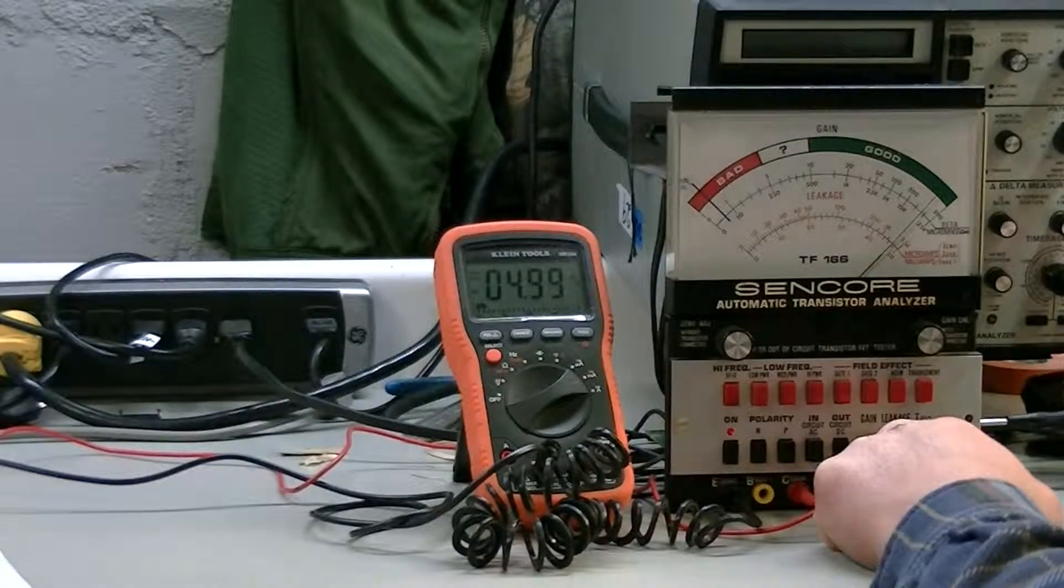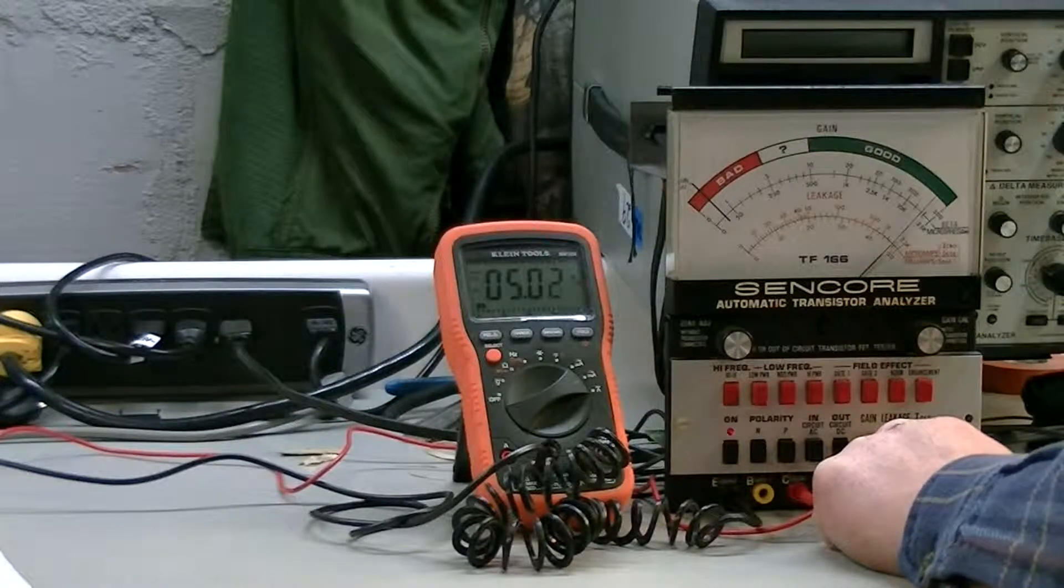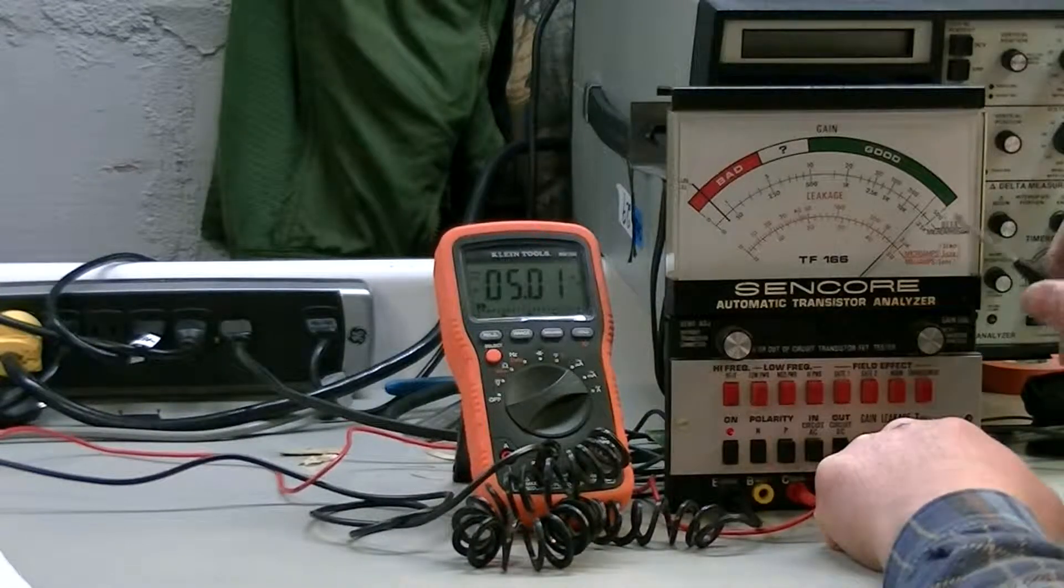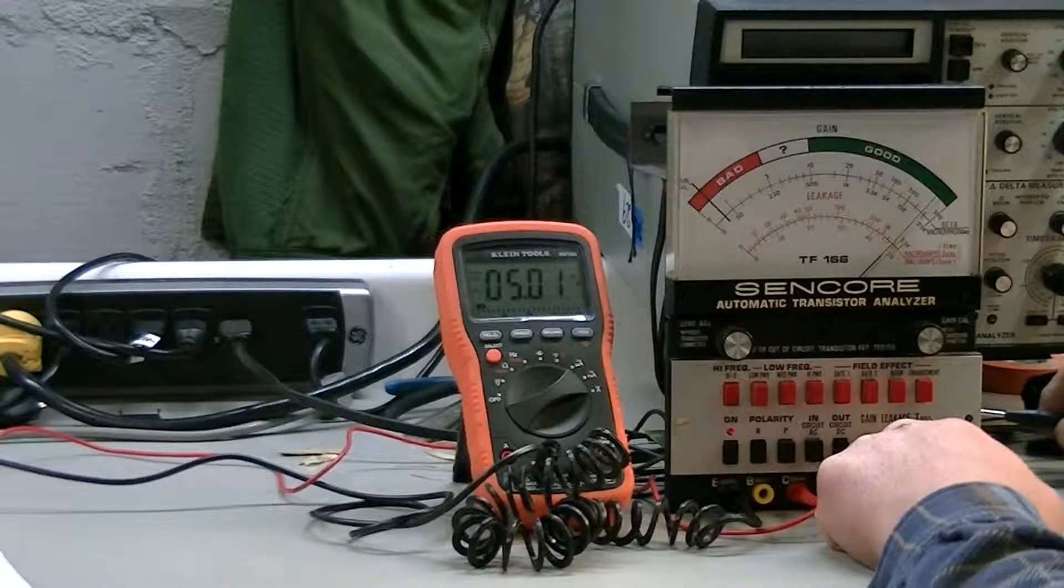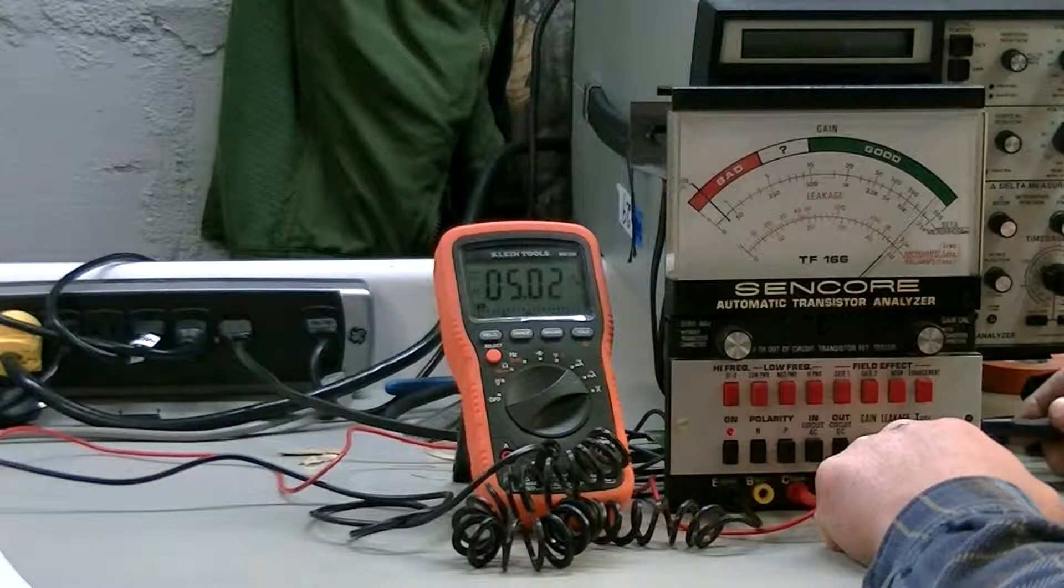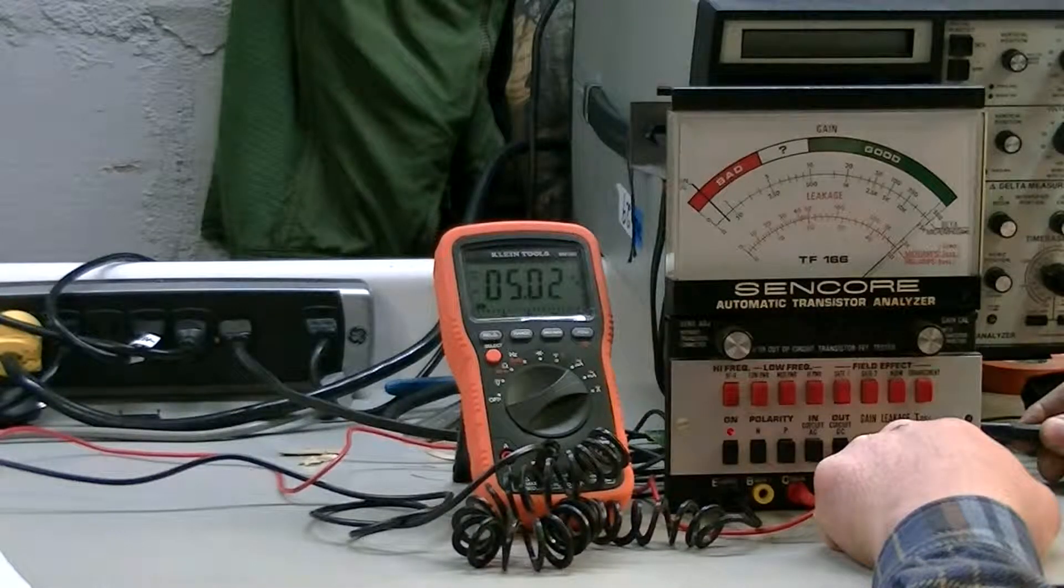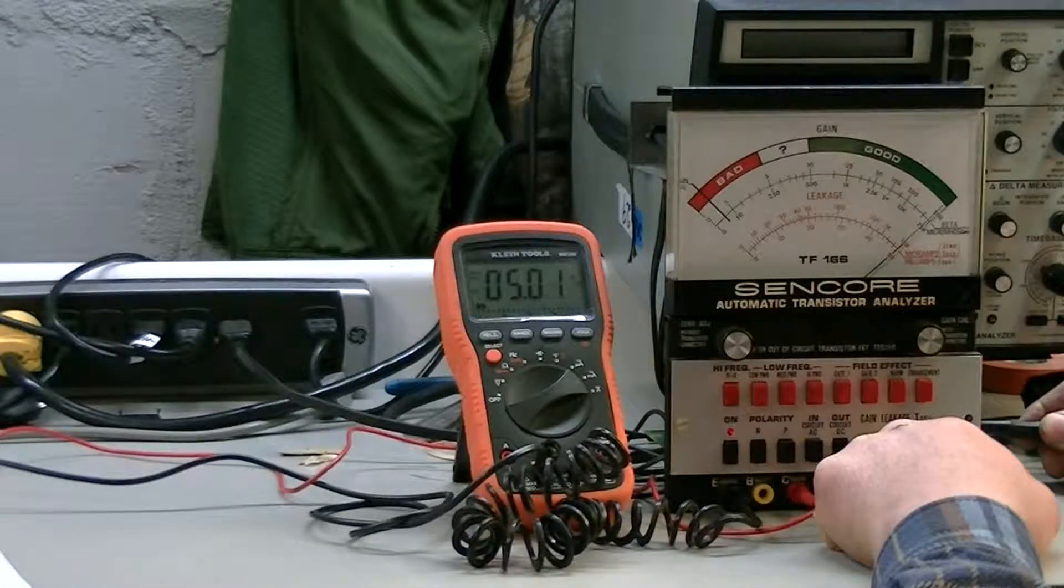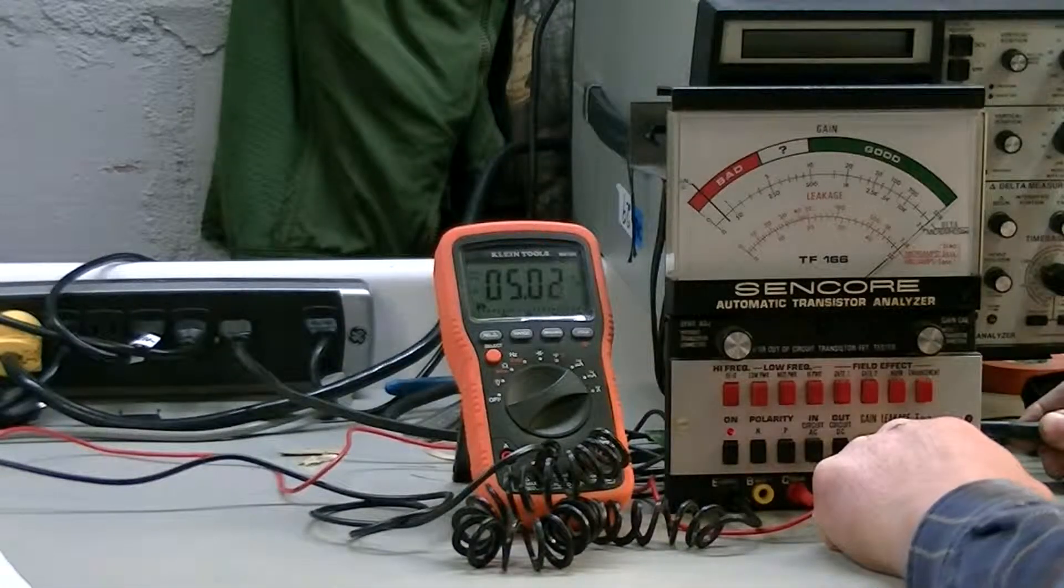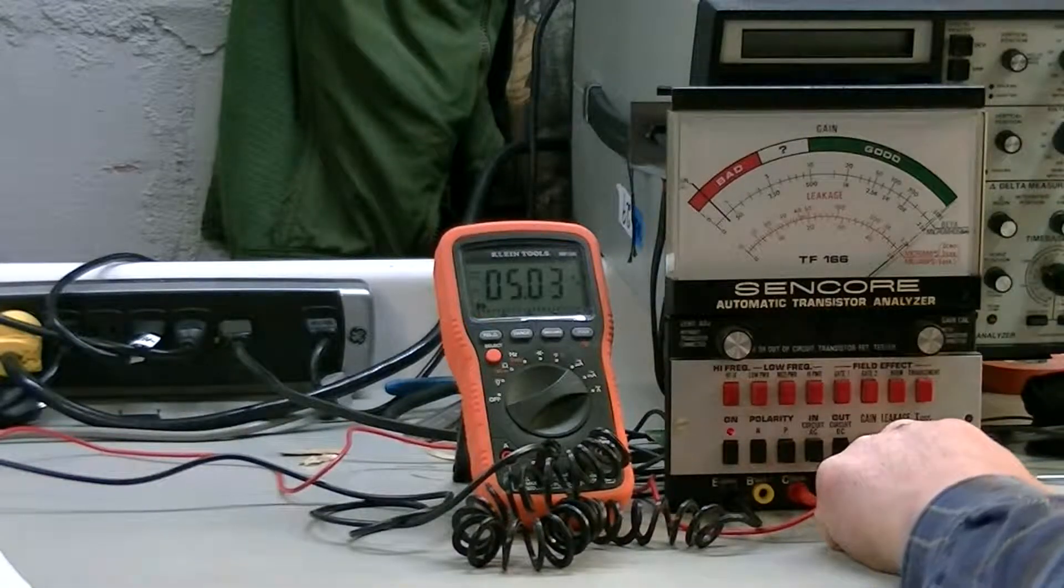And there's another pot right beside it. It is R106 and you adjust that for a beta of 500.